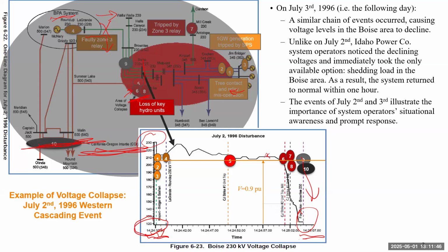So this is a very typical voltage instability or voltage collapse problem. Voltage collapse mainly describes what's happening on the system based on the phenomenon. So voltage stays near the normal voltage, but suddenly just drops in a way that cannot be controlled. And there's not a very clear precursor signal or early signal you can predict without knowing what's happening on the system. So we have to use the methods for voltage stability analysis to really figure out what happened. Then we can develop some indicator for the problem.